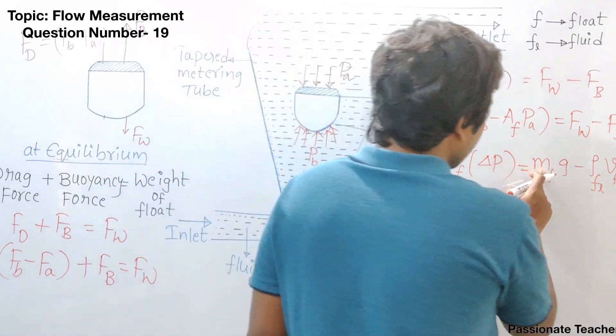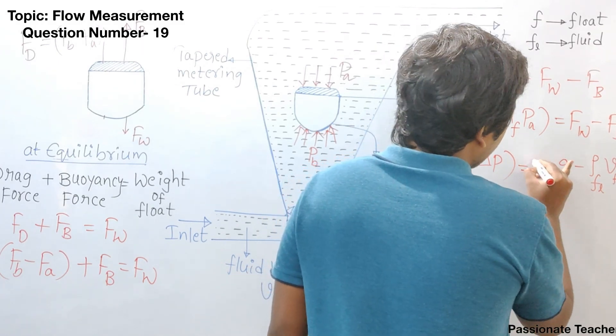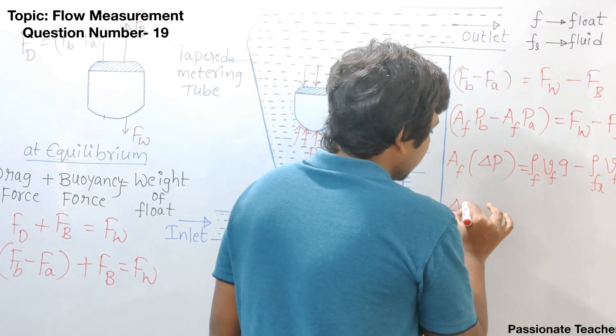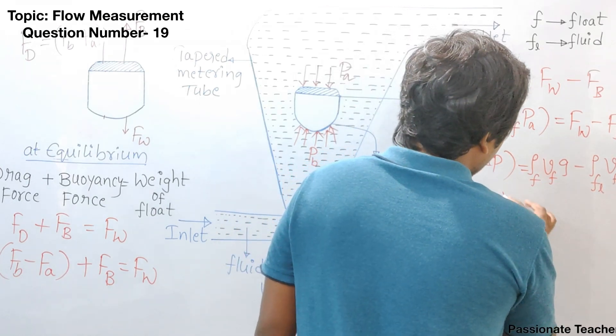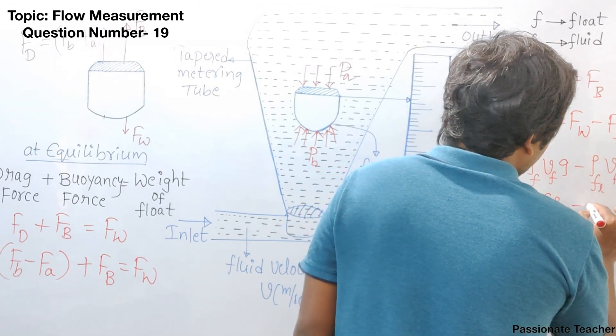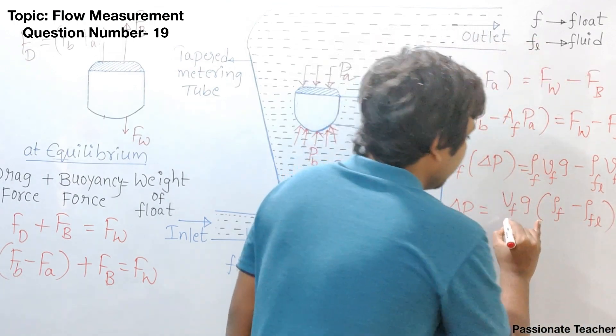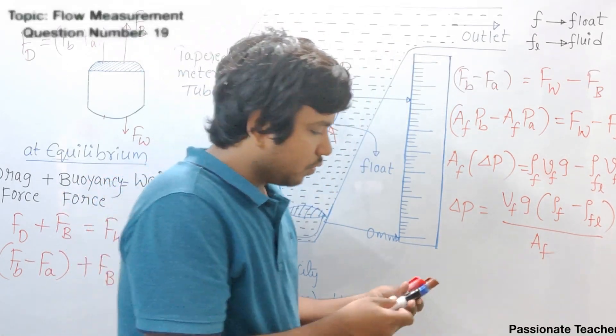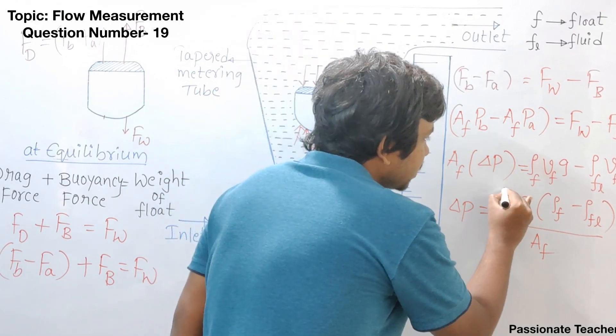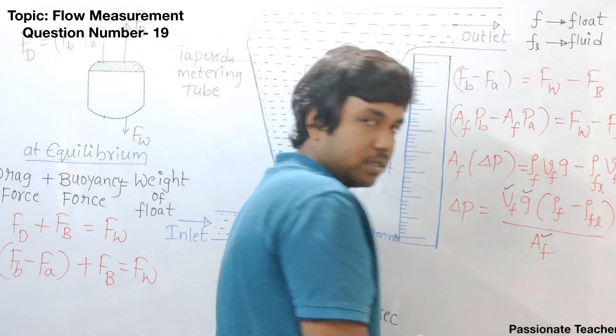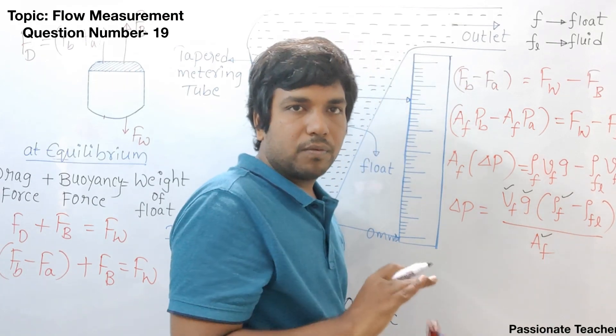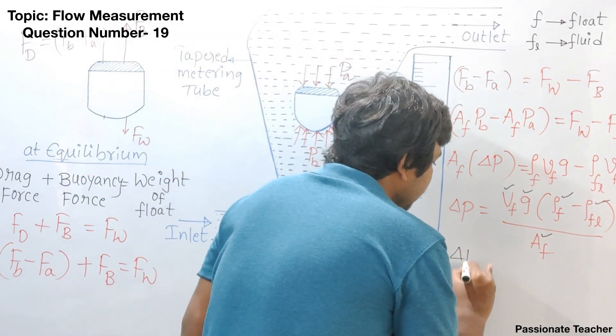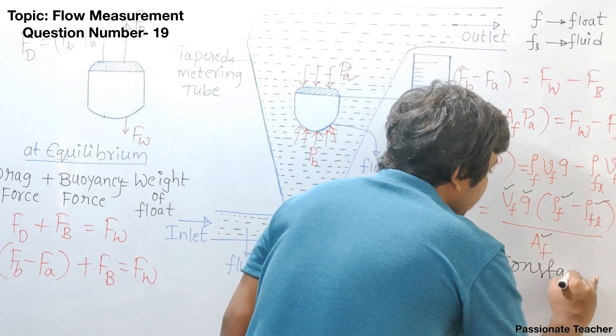The mass of the float can be written as density of the float times volume of the float. Rearranging, the differential pressure delta P equals Vf times g times (rho_float minus rho_fluid) divided by the area of the float Af. Here volume of the float is fixed, gravitational force is fixed, area of the float is fixed, density of the float is fixed, and density of the fluid is fixed — so delta P is constant.